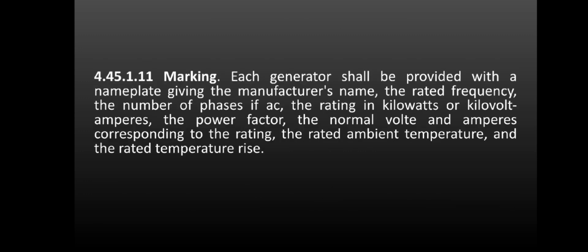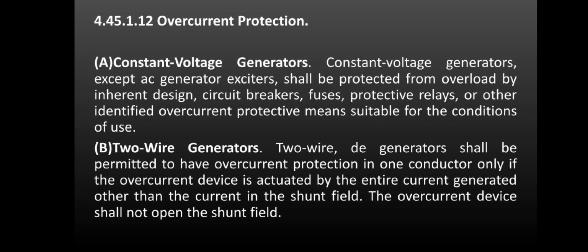Marking. Each generator shall be provided with a nameplate giving the manufacturer's name, the rated frequency, the number of phases if AC, the rating in kilowatts or kilovolt-amperes, the power factor, the normal volts and amperes corresponding to the rating, the rated ambient temperature, and the rated temperature rise. Overcurrent protection.